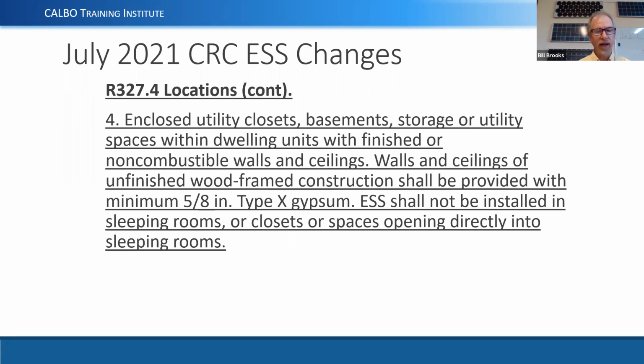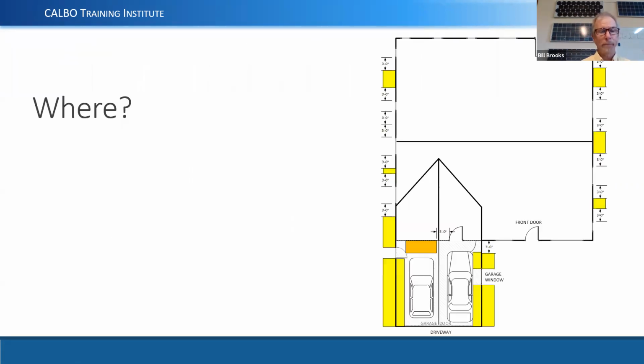Another location is enclosed inside a building: enclosed utility closets, basements, storage, and utility spaces within dwelling units with finished or non-combustible walls or ceiling. However, if you have walls and ceilings of unfinished wood frame construction, then you've got to put 5/8 type X gypsum on that exposed wood to protect the wood. And you're not allowed to install ESS in sleeping rooms or closets or spaces opening directly into sleeping rooms. So like if you had a nice, really big walk-in closet in your master bedroom, you would not be allowed to use that because that opens into the sleeping room.